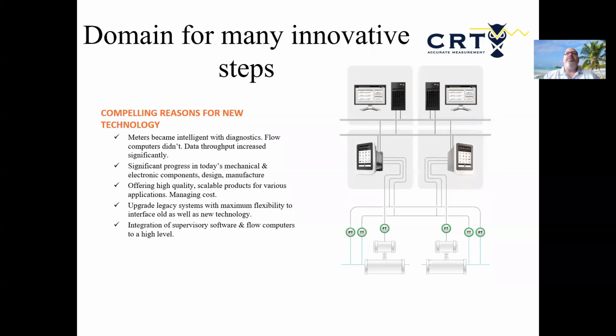But when something happens, we don't really know why it happened. Why is my meter over-registering? Why is it under-registering? As we've started to get into new technologies, one of the cool things is, let's say, a Coriolis meter. Because of the process it takes, there's a lot of diagnostic information inside. We're actually able to pull and see drive gain, tube frequency, the harmonics of the meter, and use that information to see where processes may be failing.